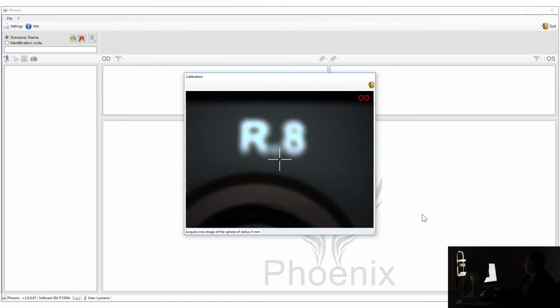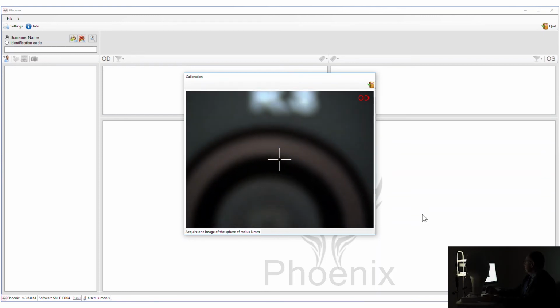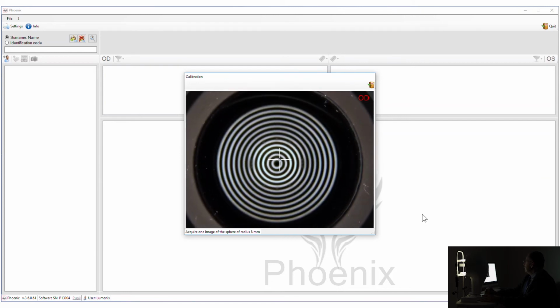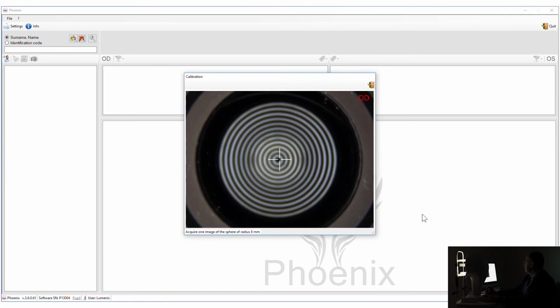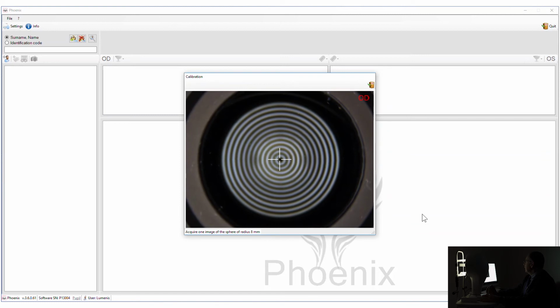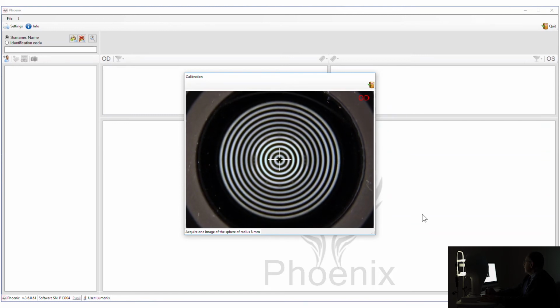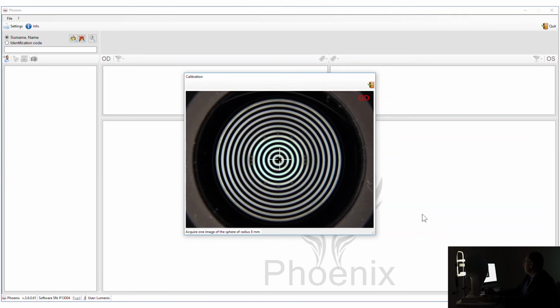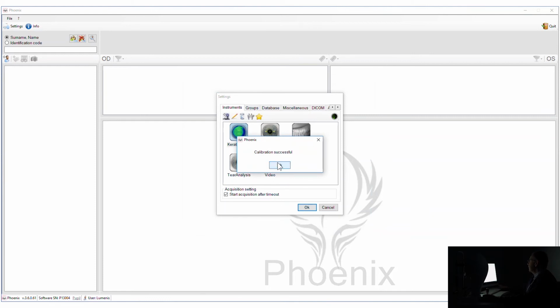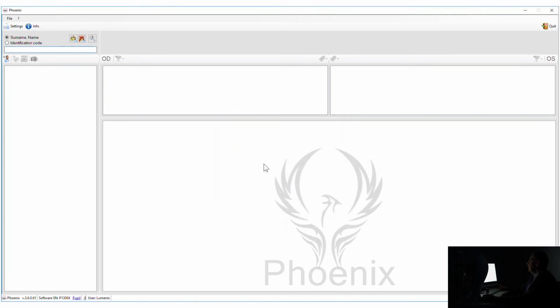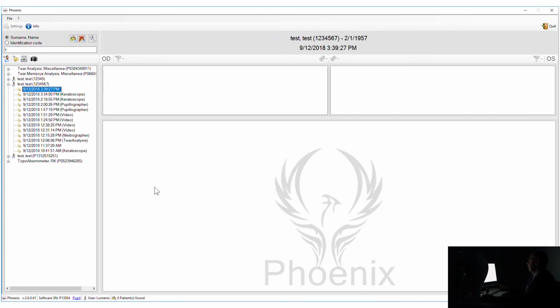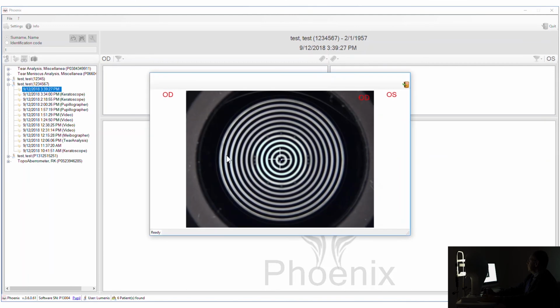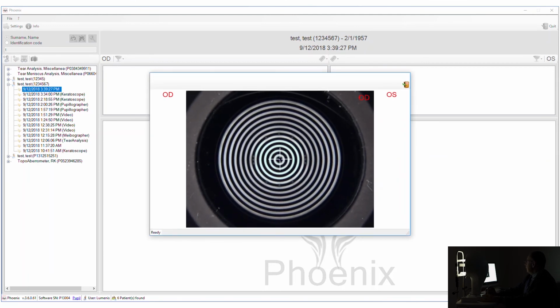Okay, we're checking that we're on the 8 millimeter. Perfect. And we're going to redo it. So let's get it right in the middle and click the button. And we're going straight in. Calibration was successful. If I get calibration successful, that's fine, but I always like to check that the calibration is good. And what I will do is another reading. So we're going to choose to do another reading, and hopefully we will get a good answer.